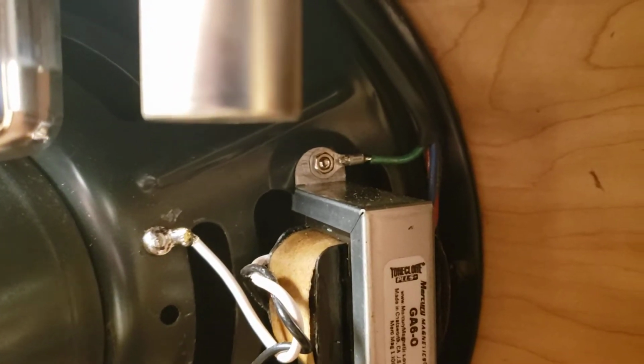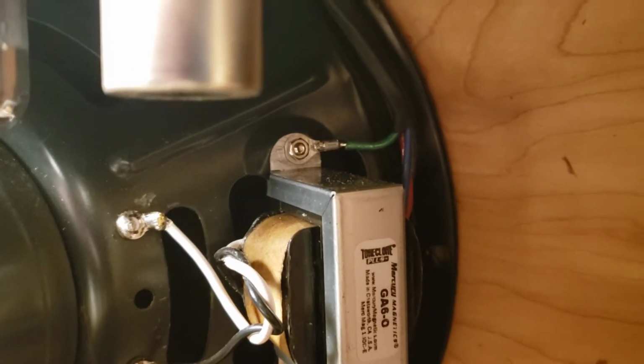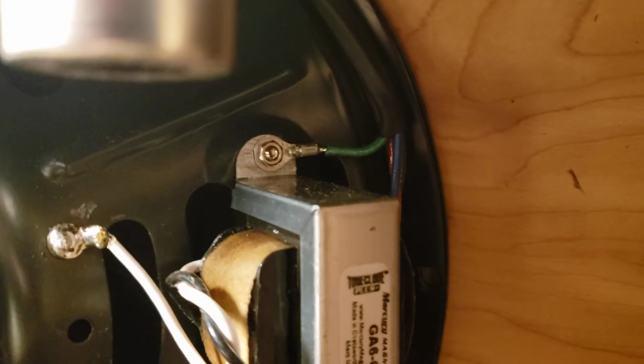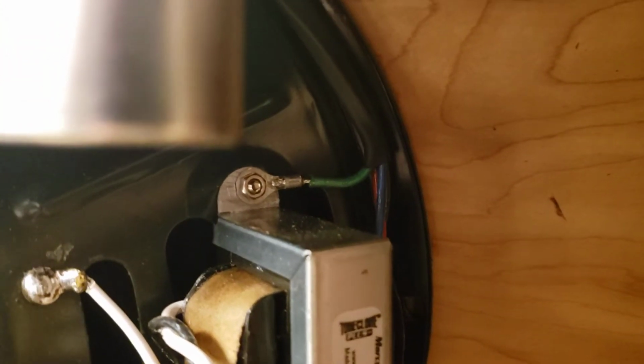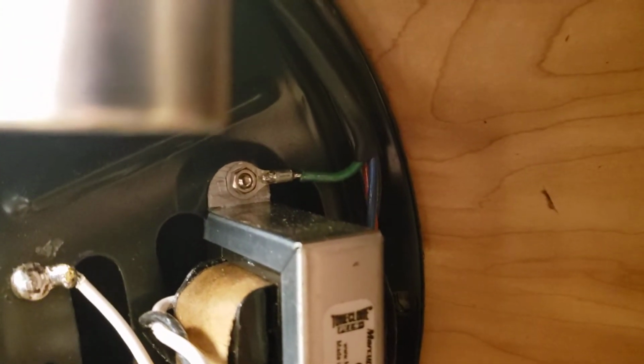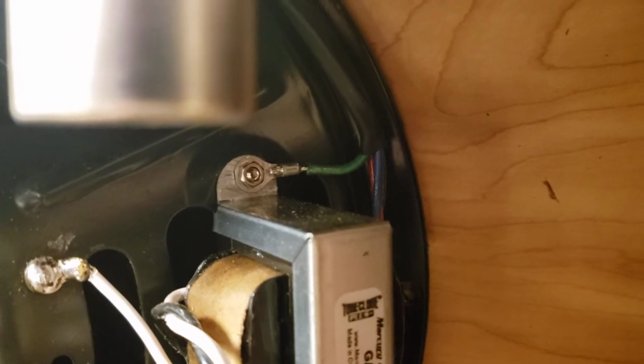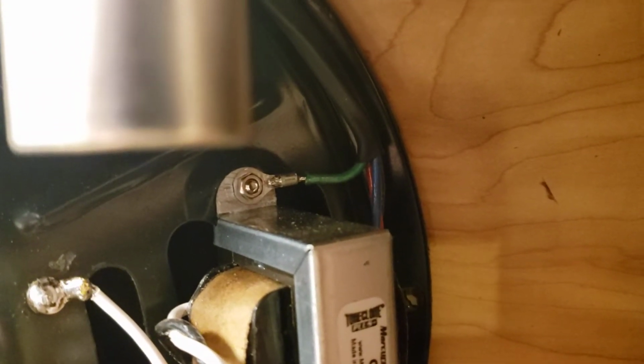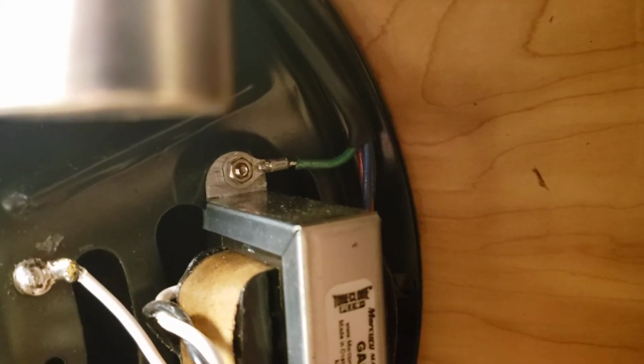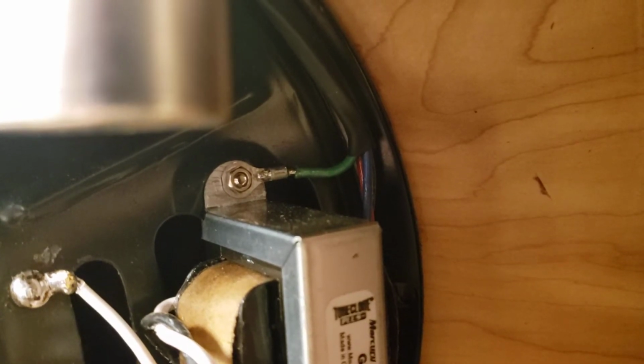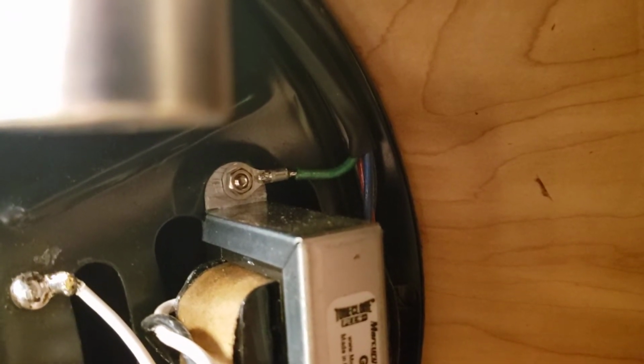So to bring things up to modern standards, I've added a fourth wire to the 3 wires coming down - that green ground wire - which is soldered into a terminal lug mounted along with the transformer to the frame of the speaker. I scraped away the varnish on the transformer before putting that lug on so it would get a nice metal-to-metal contact. Now that entire frame of the transformer is grounded.